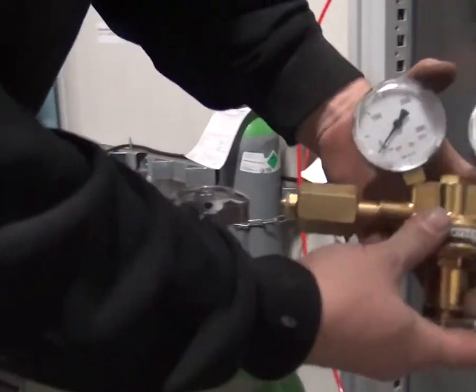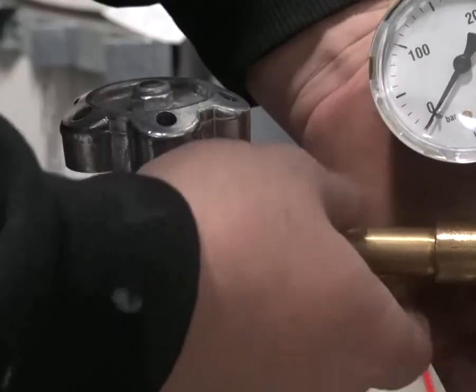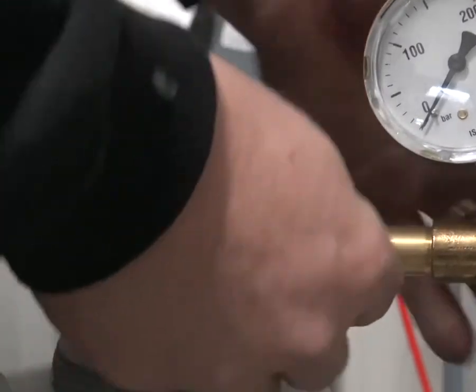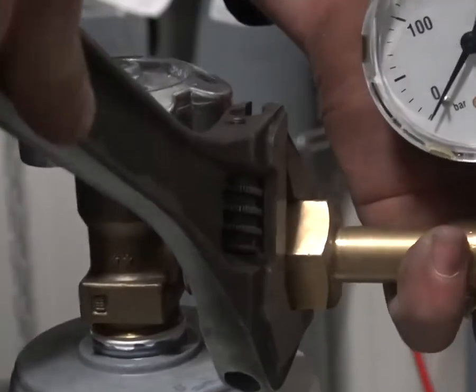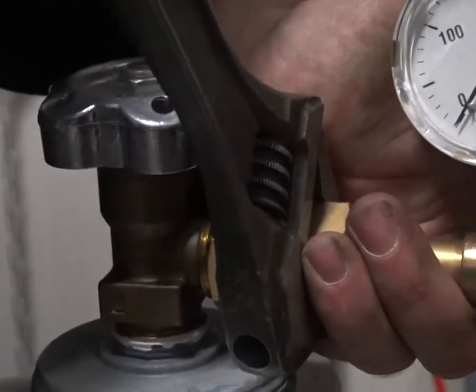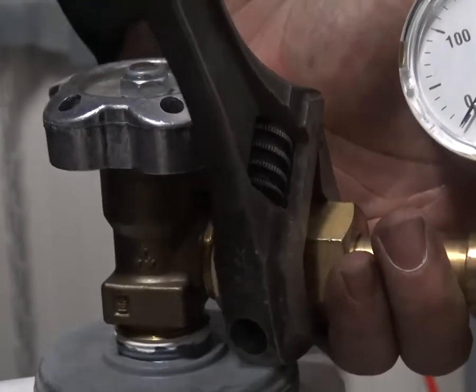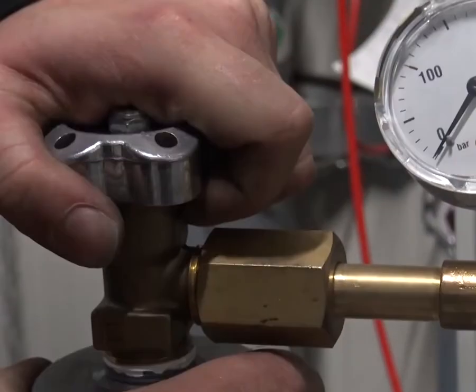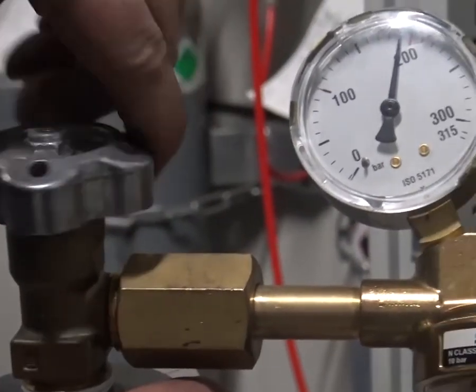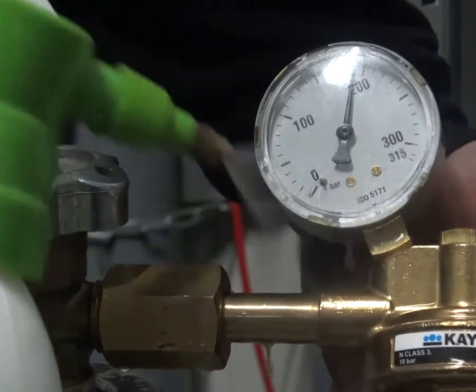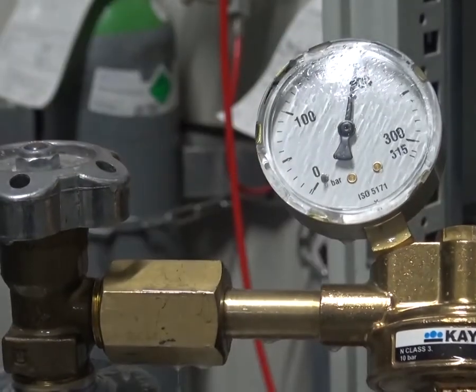You can now connect the reducer to the new calibration gas bottle. Use the adjustable spanner to ensure that the reducer is securely in place. You can check if the reducer is correctly attached by opening the bottle and spraying it with some water. If no bubbles appear, it means that the bottle is correctly attached.